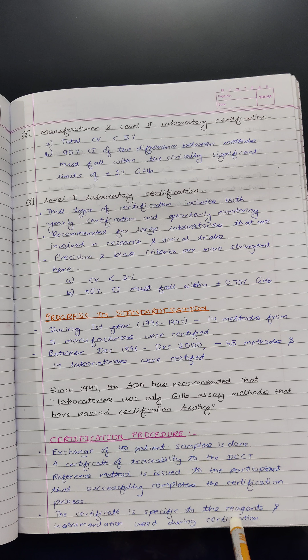Now, what is the certification procedure? Exchange of 40 patient samples is done between the NGSP and the laboratory or center which wants the NGSP certification. A certificate of traceability to the DCCT reference method is issued to the participant that successfully completes the certification process. The certificate is specific to the reagent, the instrumentation and the method used in the certification process.